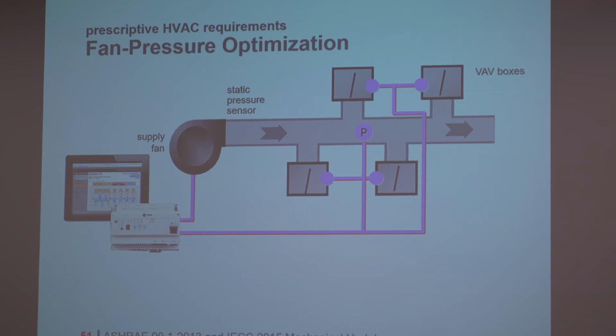The critical run moves around all the time, but having it down the ductwork somewhere is sort of trying to reflect the average pressure at the boxes that are downstream of it. And so the idea is if you can place that so that its set point is no higher than 1.2, then you're far enough down the duct that you're able to get a pretty good representation of the zone's pressure requirements. So there's two ways to do it. One of them is this 1.2 maximum set point. The other one is to have a method within your control system of identifying rogue zones and removing them from the optimization logic.